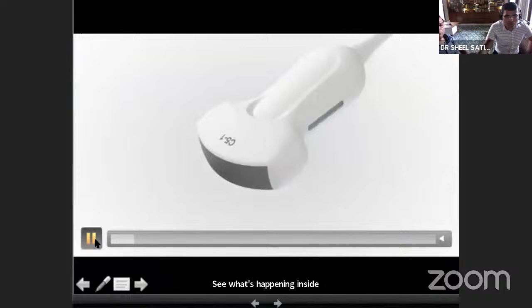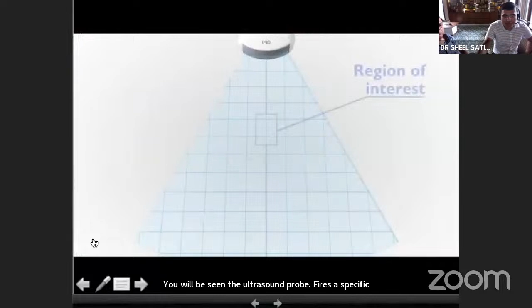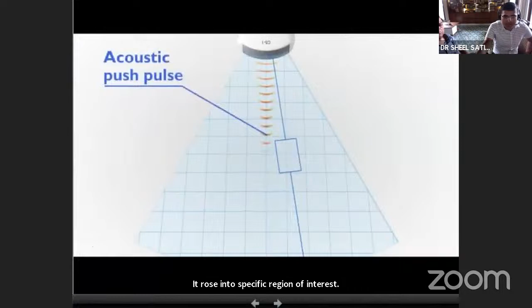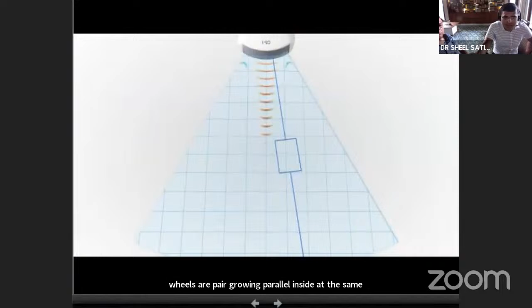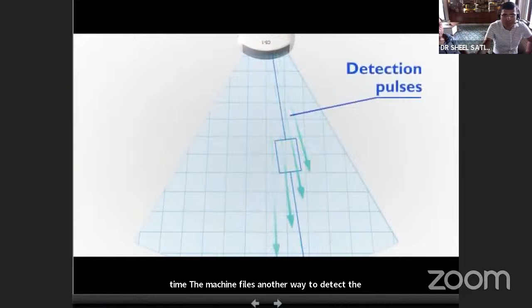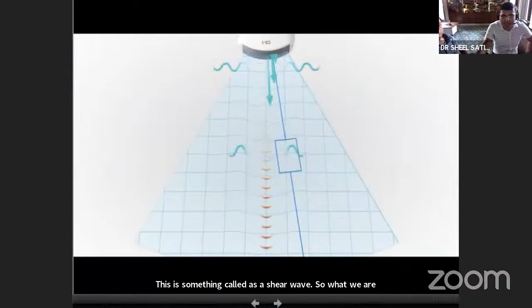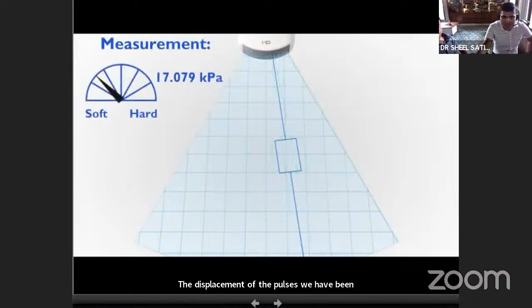Now, going back, what is important is how does this generate the induction wave? See, what's happening inside is you will be seeing the ultrasound probe fires a specific beam. This beam goes inside the soft tissue. It goes into a specific region of interest. Once these waves are going parallel inside, at the same time, the machine fires another wave to detect the displacement of the tissue. This is something called a shear wave. So what we are doing, we are sending the machine pulses inside. The displacement of the pulses is being measured. This is as simple as it is.